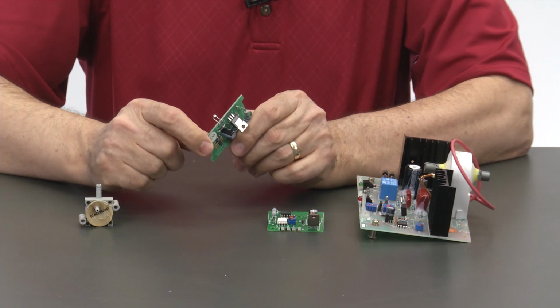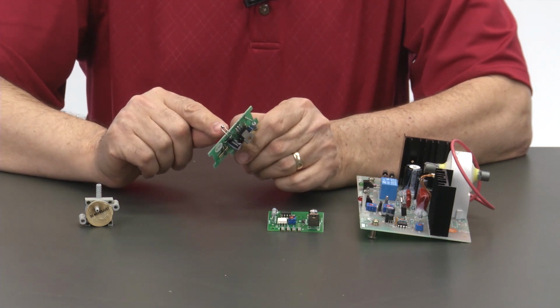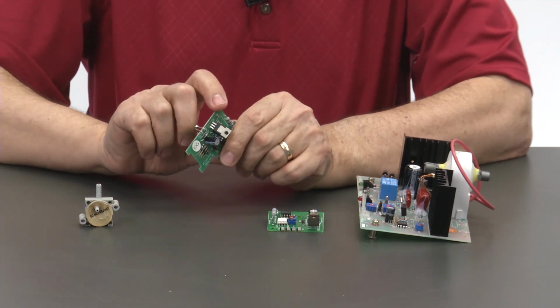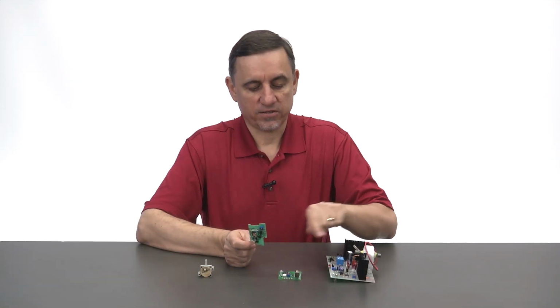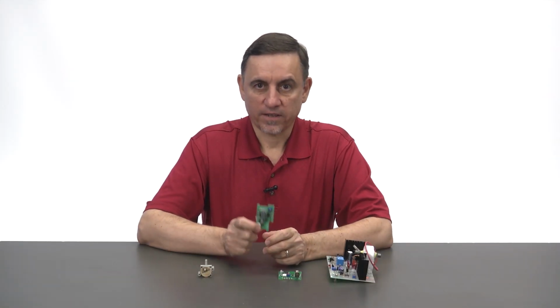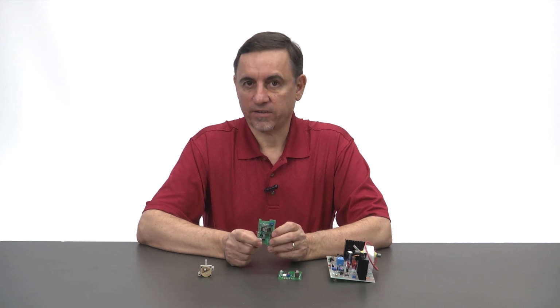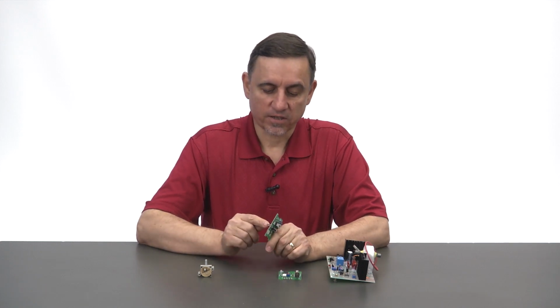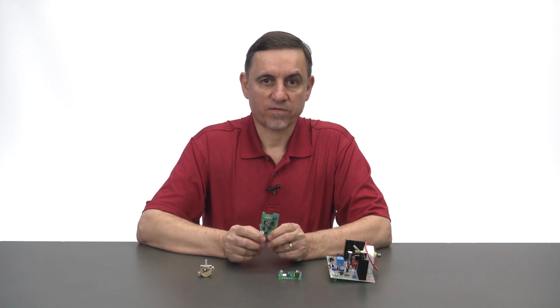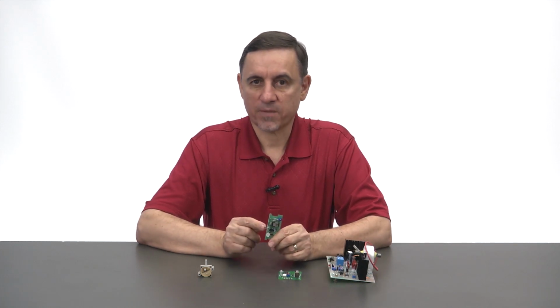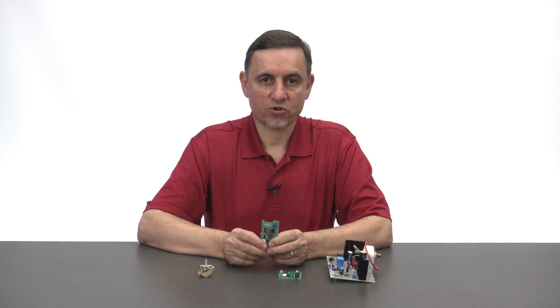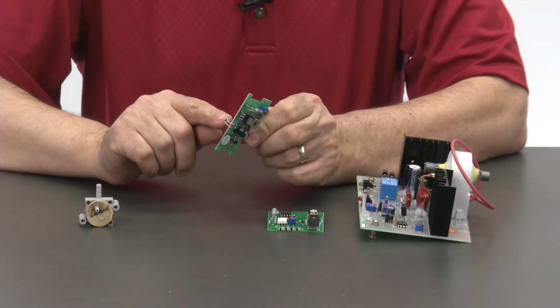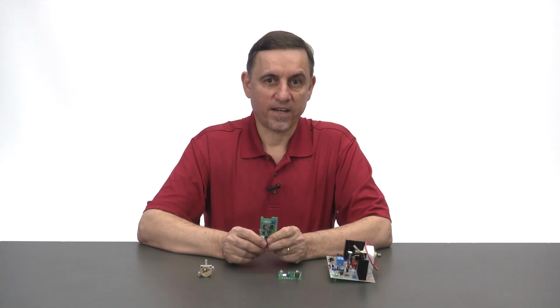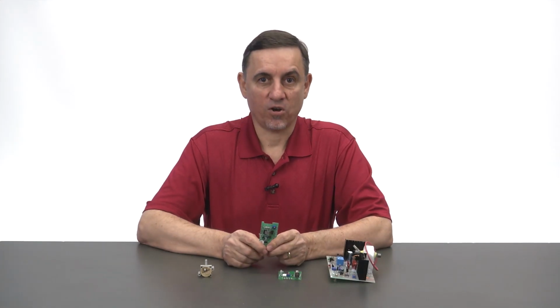All right, so now we're on to airflow sensor number 2. Now this one is an electronic style, the same as the next 2, version 3 and version 4. They're all electronic style sensors, and the way they work is there's a little sensor back here, and when you first turn the air cleaner on, the sensor warms up, reaches a very specific temperature, and then it turns off the air cleaner. It then sits and waits until air blows across it and cools it off, and then it turns the air cleaner back on.